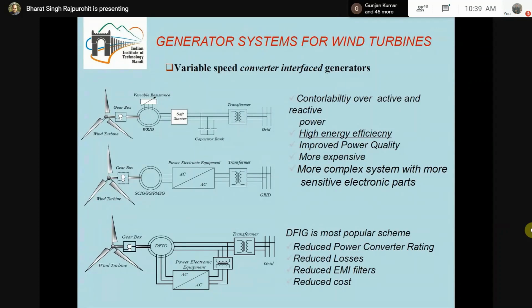The middle figure consists of a generator which is a squirrel cage induction generator, or a synchronous generator, or a permanent magnet synchronous generator. In PMSG, generally the gearbox is optional. The construction of the squirrel cage induction generator is already known: the rotor has a squirrel cage, a short circuited rotor. Now here you can see that the stator connections are connected to a power electronic circuit, which is connected to the electric grid. This power electronic circuit, shown here as AC to AC, what does that mean? This power electronic converter is able to take the AC power coming from the generator, of any frequency and any voltage level, and transform it into AC once again, at a specified voltage and specified frequency, and that is why it can be connected to the grid and the power can be fed to the grid.